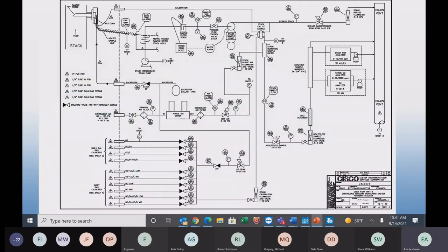So let's look at a typical print here. Here's our sample pump. And again, everything to the left here is under vacuum. So the guy changes the filter here, doesn't get it tight, doesn't get it set right, and there's a common place for a leak right there.